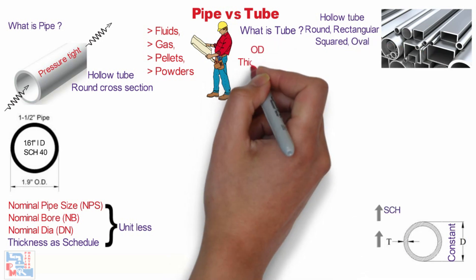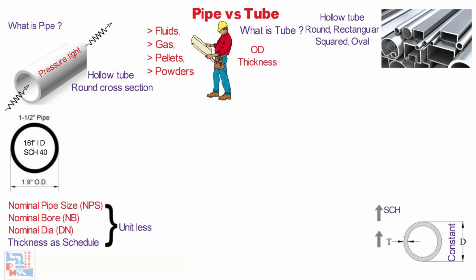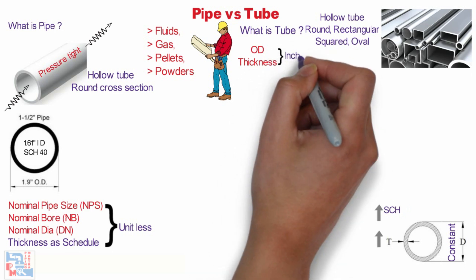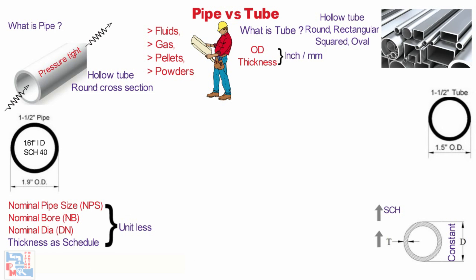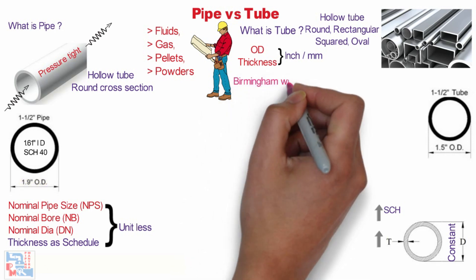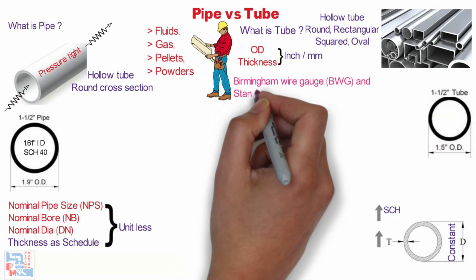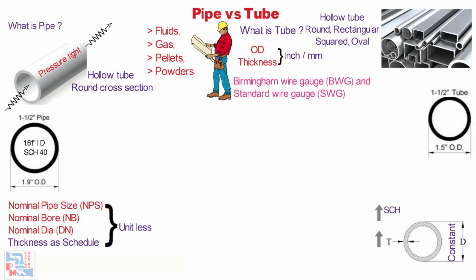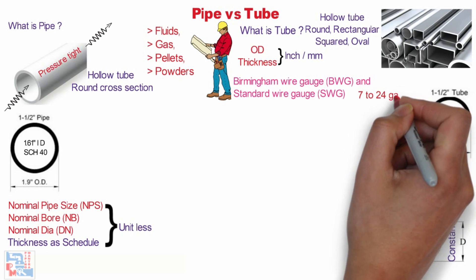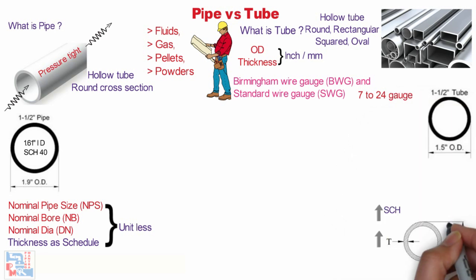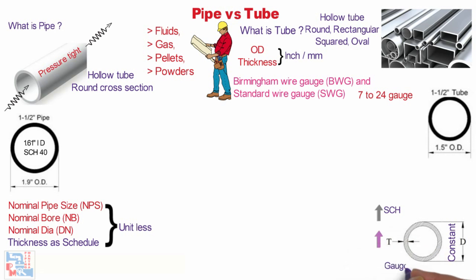Tubes are measured by outside diameter (OD) and wall thickness (WT), expressed as true dimensional values in inches or millimeters. As you can see here, a 1.5 inch tube has an OD of 1.5 inches, whereas in the case of a pipe it was 1.9 inches OD. Usually, the thickness of a tube is specified in gauge — Birmingham wire gauge (BWG) and standard wire gauge (SWG) — ranging from 0 to 36, but in industry we use 7 to 24 majorly. For a given size of tube, the outside diameter stays constant, and wall thickness increases with a smaller gauge number.